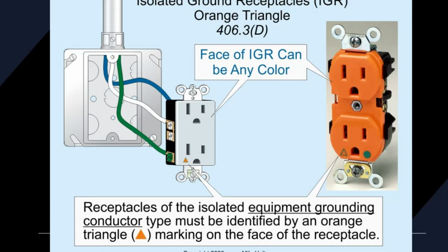All right, isolated ground receptacles, orange triangle. So you've got the green triangle. Normally these are orange. You could also have an orange triangle. And what that means is you have a dedicated, isolated equipment ground, I should say. So I have a ground that's bonded to the metal in the box. It's bonded to the pipe. It's bonded to the sub panel. It goes everywhere. This isolated equipment ground goes straight back to the panel, and it doesn't have to bond to anything. And the reason they do that is for sensitive electronic equipment. It keeps the noise, if you will, off the ground. It keeps all the stray voltage that the bond might contain off there, and it's a clean ground for computer equipment or sensitive equipment.